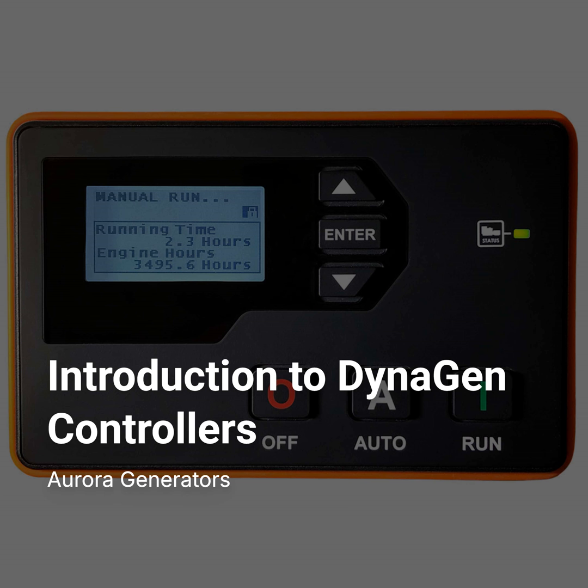And what about more automated operation, like a generator kicking in automatically on power failure? That's where the auto mode really shines. Some controllers have a neat pre-start feature where the fuel relay can energize before cranking starts. Why would you do that? It lets the engine's ECM, the electronic control module, power up and be ready to go instantly when the starter engages. Helps with faster starts on electronic engines.